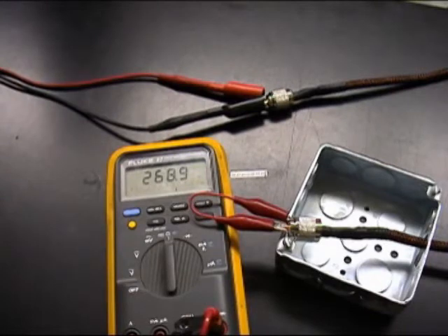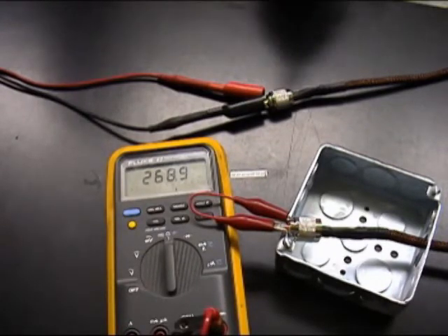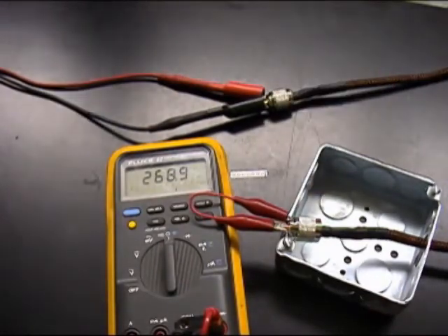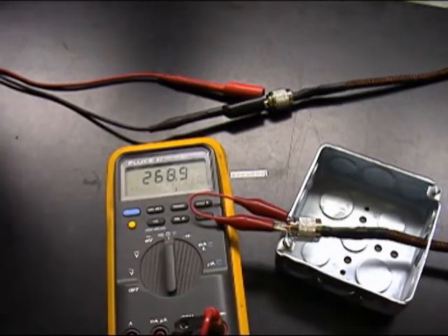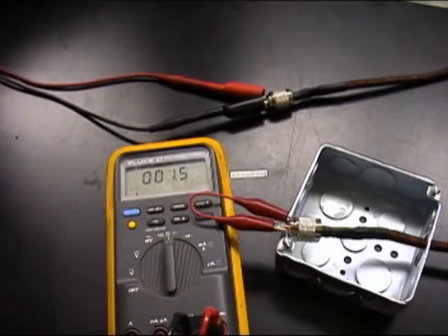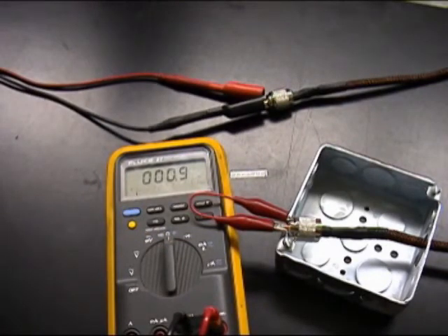If you get a higher than expected resistance reading, which would be anything over the approximately 10 ohms per 1,000 feet, then the outer braid was improperly sanded or not sanded at all under the outer or shield crimp ferrule. Or the braid wire between the connectors was damaged. If you do not get a stable low resistance reading, then the cable or one or both of the connectors will have to be replaced.